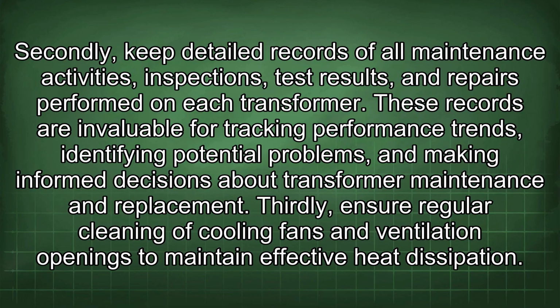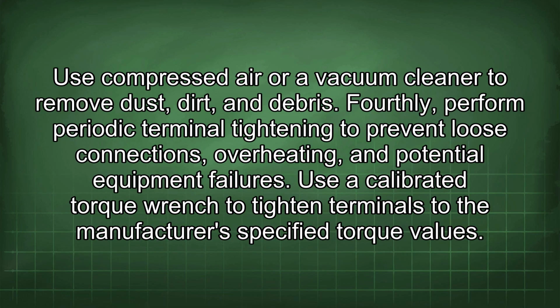Thirdly, ensure regular cleaning of cooling fans and ventilation openings to maintain effective heat dissipation. Use compressed air or a vacuum cleaner to remove dust, dirt, and debris. Fourthly, perform periodic terminal tightening to prevent loose connections, overheating, and potential equipment failures. Use a calibrated torque wrench to tighten terminals to the manufacturer's specified torque values.